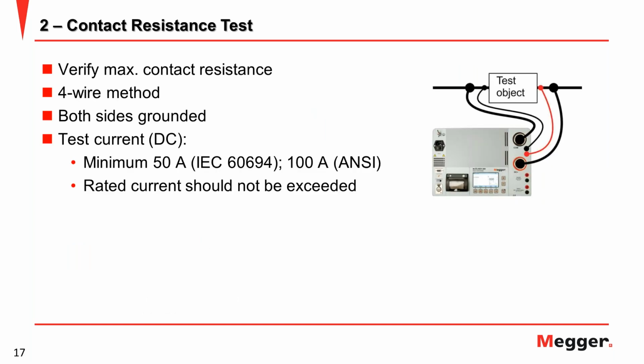Next, the contact resistance test. This is also important to be tested on the circuit breaker because the contact resistance test is very important for contacts that carry a large amount of current, like a circuit breaker. Higher contact resistance leads to higher losses. So if you have higher resistance, you will get higher losses, lower current carrying capacity and dangerous hotspots in the substation. It will impact the heating on the connection of the main contact. If this continues for a long time, it will reduce the lifetime of the breaker.